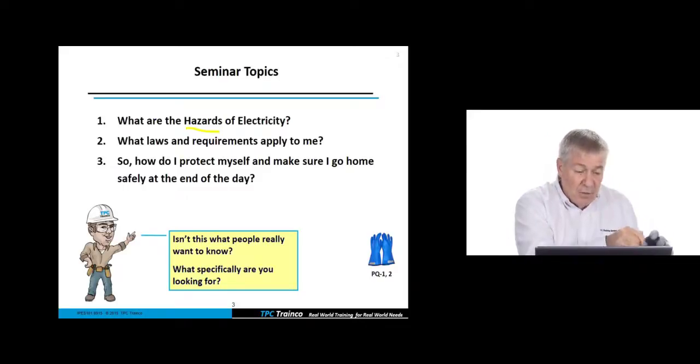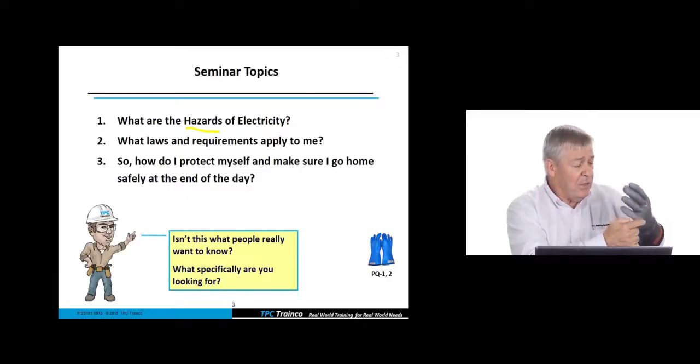And I see I have a question here from Marty again. What about dexterity? And that's a great question. And that begins with the proper size of rubber glove. If I take a tape measure and measure right around my knuckle area, when that tape measure comes back and touches itself, whatever number I see, that's the size glove I should purchase.